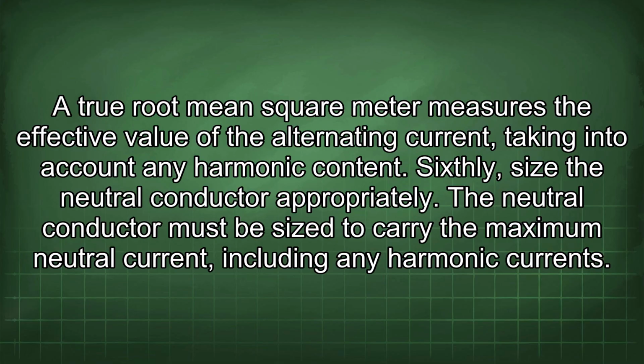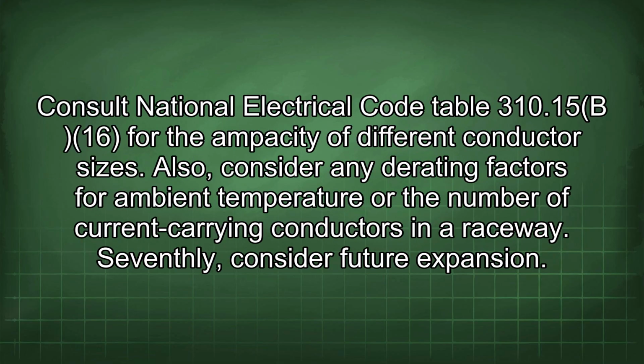Sixthly, size the neutral conductor appropriately. The neutral conductor must be sized to carry the maximum neutral current, including any harmonic currents. Consult National Electrical Code Table 310.15(B)(16) for the ampacity of different conductor sizes. Also, consider any derating factors for ambient temperature or the number of current-carrying conductors in a raceway.